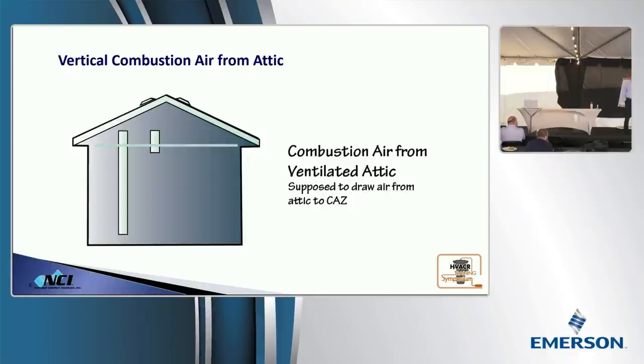Don't take my word for this. I'm going to talk about some test instruments here in a couple seconds you can use to test this. You guys can get toilet paper. You got to use single ply, though. It's got to be John Wayne type. Use single ply, hold it at the bottom of that duct, and watch which way it goes. I promise you, if you hold it at the bottom of that duct, it's going to suck right up in it. Just test it and see. It's really cool. You'll lose a lot of toilet paper up into an attic.